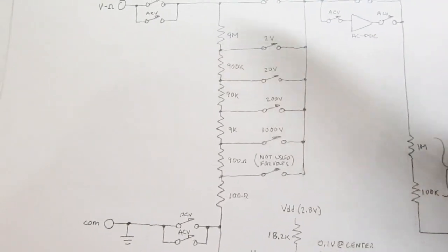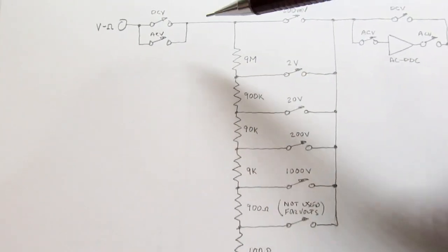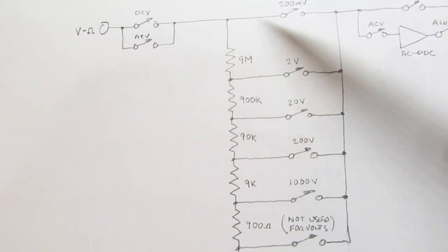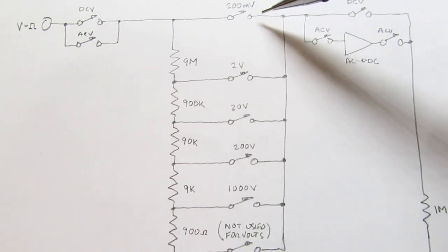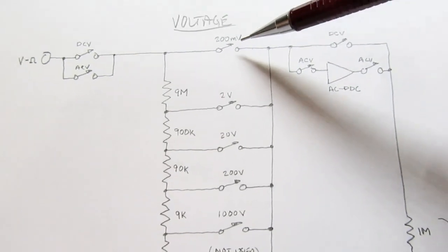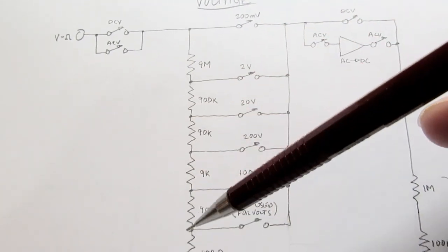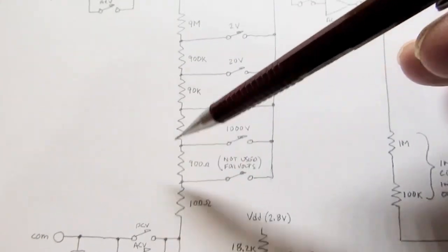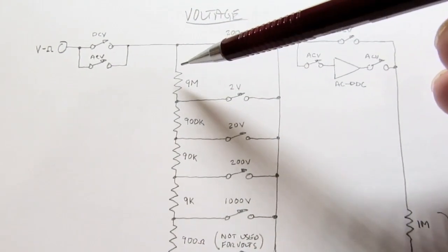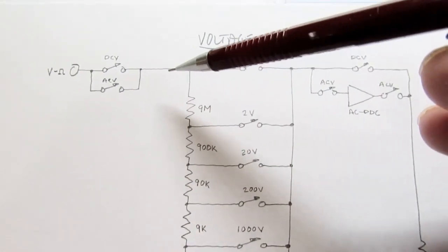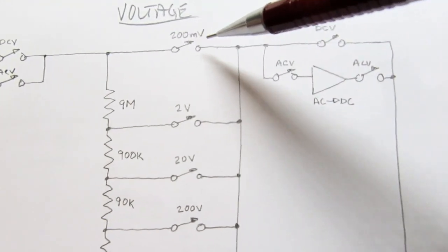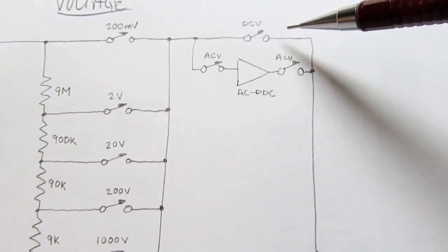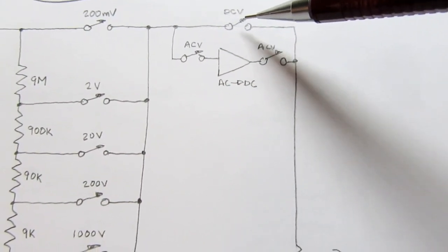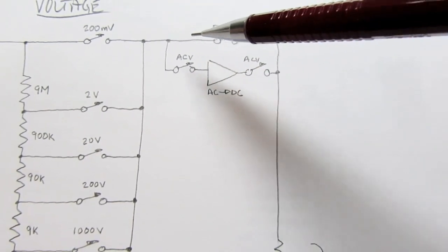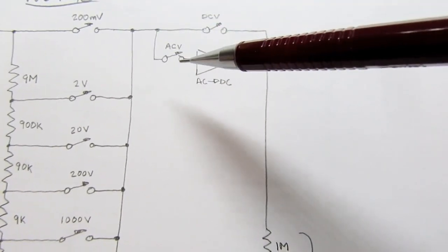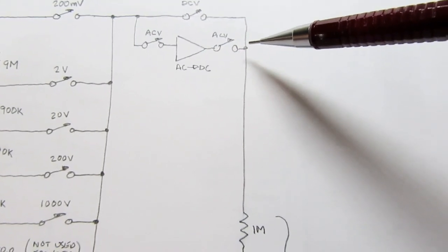So let's say you're applying a signal that's less than 200 millivolts. You would close this switch up here. That would put you in the 200 millivolt range, and then this whole divider is sort of ignored. It just acts as a high impedance load across whatever you're measuring, but you actually don't divide anything down. The voltage just comes straight out through the 200 millivolt range switch, and then depending on whether you're in DC or AC volts, you can either go straight through or you have to detour through the AC to DC converter.